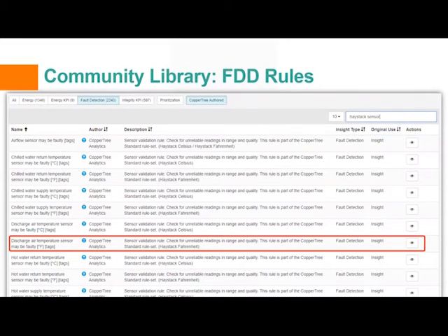So the idea then is that the tags that Michael talked about, which have been added to discharge air temperature sensors in the building, will be used to map this rule to those sensors. And that can be done with the click of 2 buttons. It's not a manual process, and that's why tagging of points is such a key piece to analytics implementation.